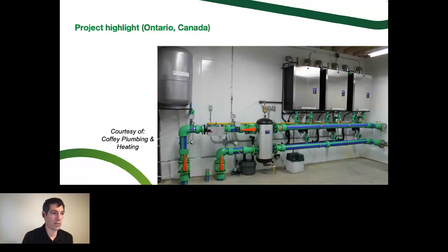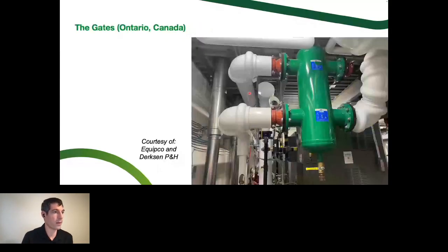One boiler or three boilers could be on if you've got enough of the header right here, and this is sized for all three of those flow rates combined. We're not going to have any issues choking flow to any of these three boilers as they come on. And you could put a flow meter right here and see that there's 0 GPM flow on that screen of that pump. As an example, maybe even when these boilers are calling, that's properly separated.